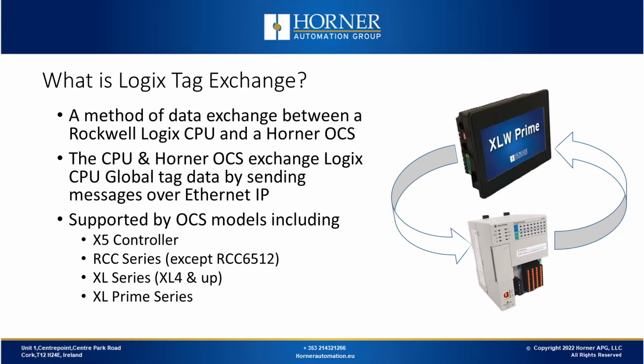So what is Logix tag exchange? Logix tag exchange is a method of data communications between a Rockwell Logix PLC CPU and a Horner OCS for exchanging tag data for variables that reside within the Logix CPU. It uses Ethernet IP type messaging to accomplish that. This feature is supported by a variety of OCS models, including the Micro OCS X5, the entire RCC series except for the 6512, the XL series for the XL4 up, and the entire XL Prime series. It's not compatible with the XLE, XLT, or the Micro OCS series aside from the X5.